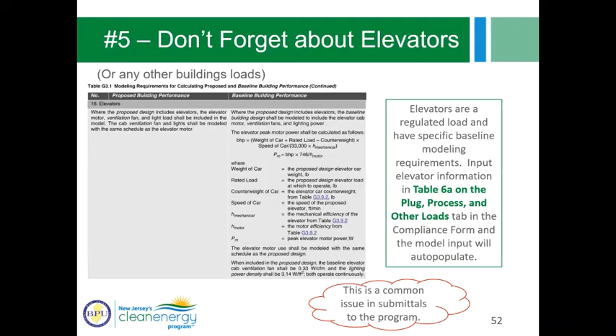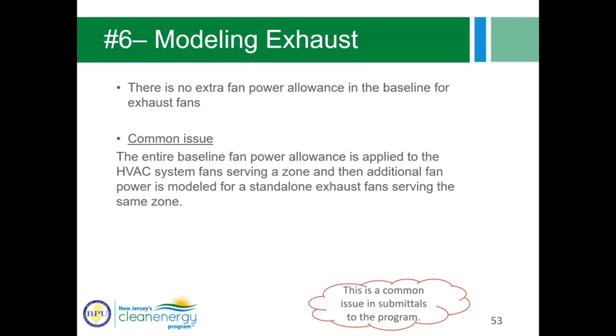All right, here is another. This is a very, very common issue. So there's no extra fan power allowance in the baseline for exhaust fans. The common issue is essentially that the entire baseline fan power allowance is applied to the HVAC system fans serving a zone. So for an example, a submitter will model their dwelling unit PTAC as 0.3 watts per CFM per the rules of Appendix G, which is correct. But then they'll also model the exhaust fans and include kW per CFM or fan power for those exhaust fans in the baseline. And that's not allowed. So you've got your 0.3 watts per CFM allowance, and you don't get anything extra for those exhaust fans.